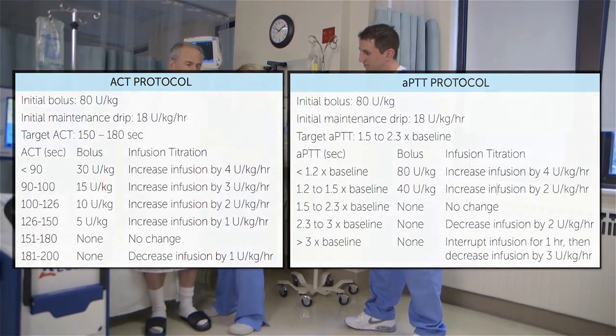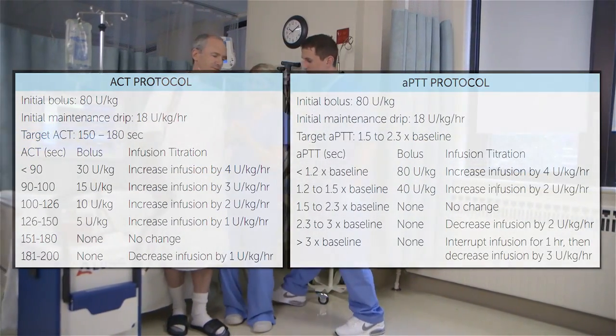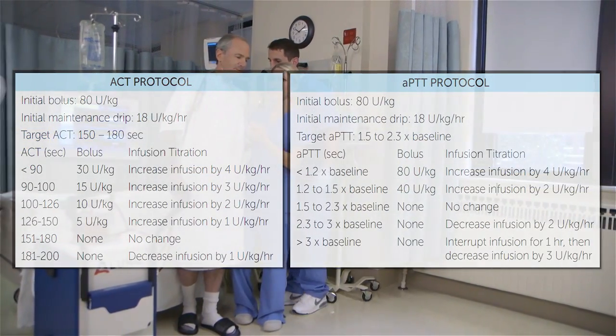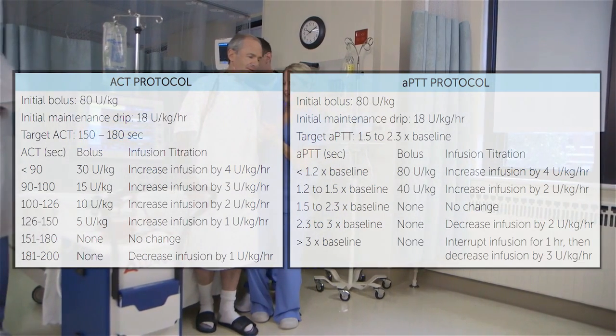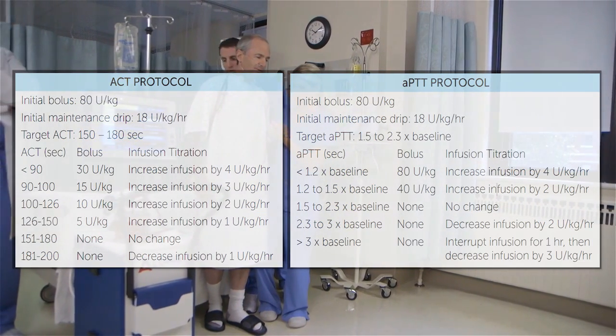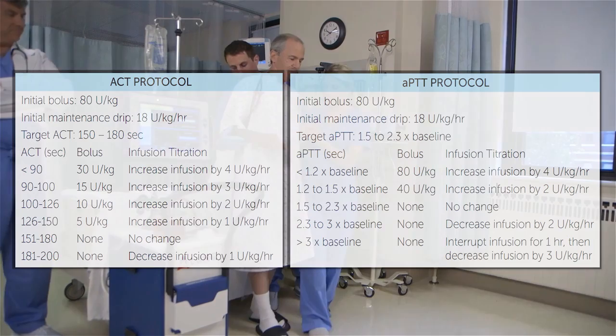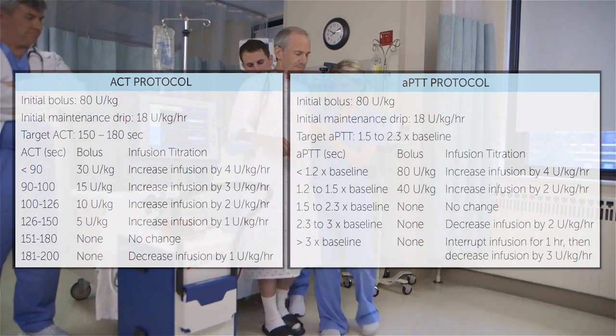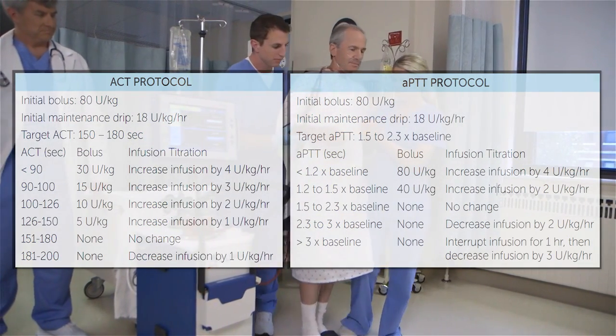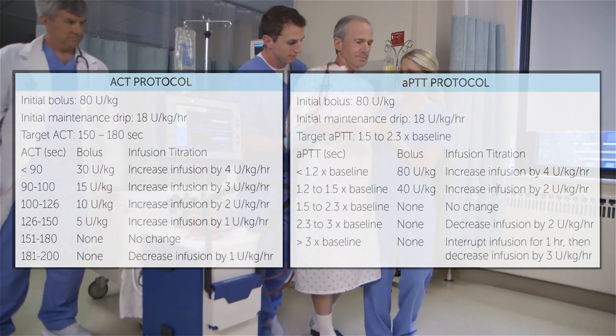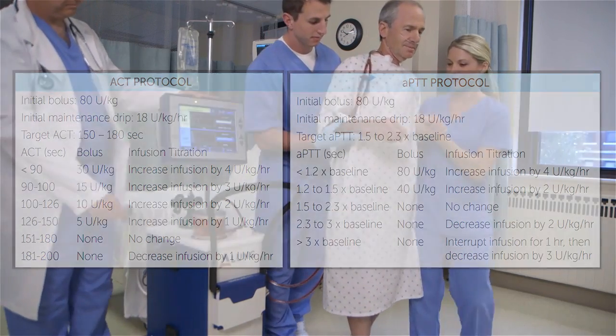Systemic anticoagulation is required for Hemolung therapy. Prior to connecting to the Hemolung RAS, a target activated clotting time of 150 to 180 seconds, or activated partial thromboplastin time of 1.5 to 2.3 times baseline, is recommended.